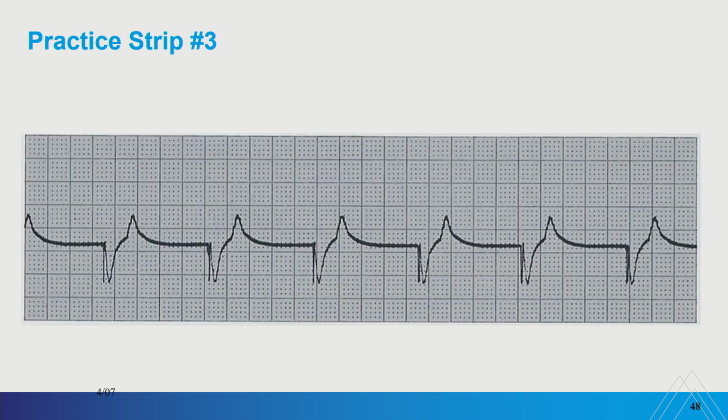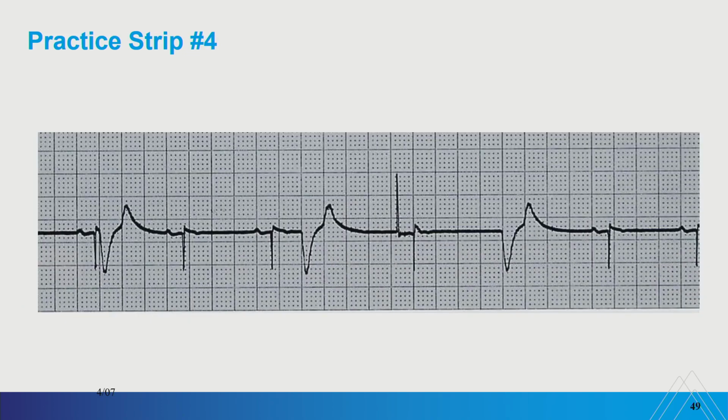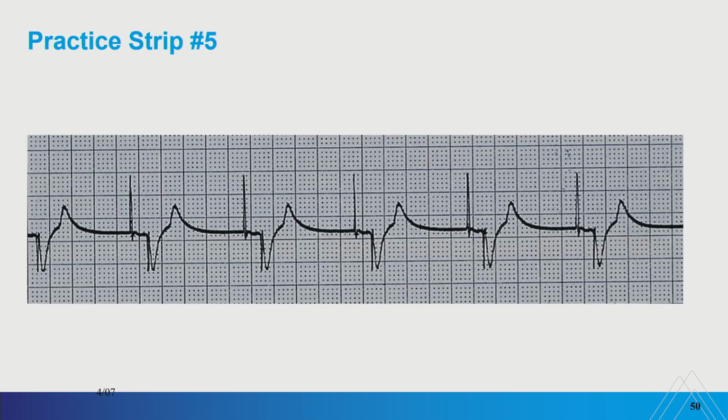What kind of pacing? V-paced, okay. This is a problem. What's the problem? Failure to capture the ventricle. Actually, if I look here, it's probably failure to capture the atrium also. So I need to turn the mA up, but check all of my connections also.